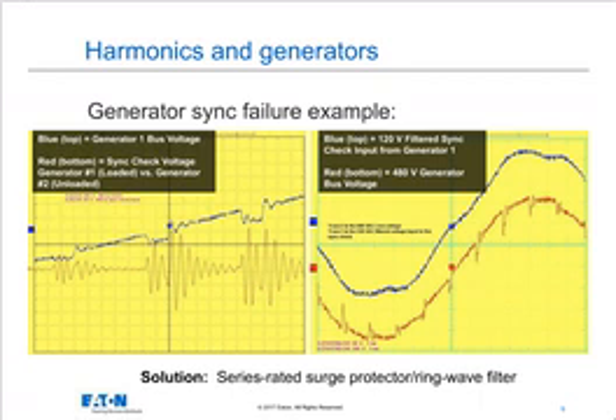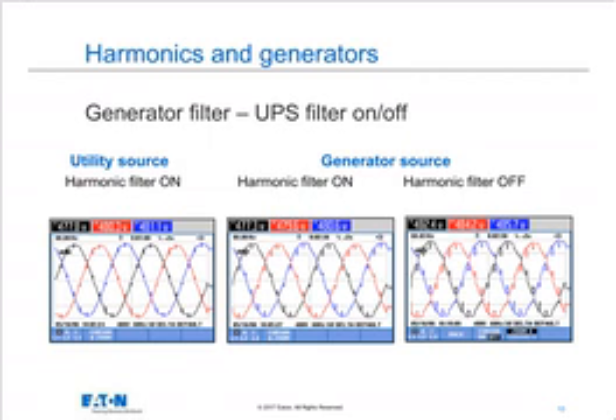A couple different solutions for that. One would be to change the technology in the UPS, and Ed's going to address that, and I'll address it a little bit here. But the other way that we did it, sort of a Band-Aid approach at that time, was just to clean up the synchronizing voltage with a smaller fix, or cleaning up the actual sync check voltage. Now, I say it's a Band-Aid approach because we were very careful to make sure that we were still able to synchronize and not shift anything out of sorts, so that when we did parallel these two generators, they didn't blow each other apart, because that could have been obviously very problematic. So we looked at it and we compared the two, and we made the decision that a short-term Band-Aid approach would work, and then we looked at other methods of reducing the overall harmonics in the system.